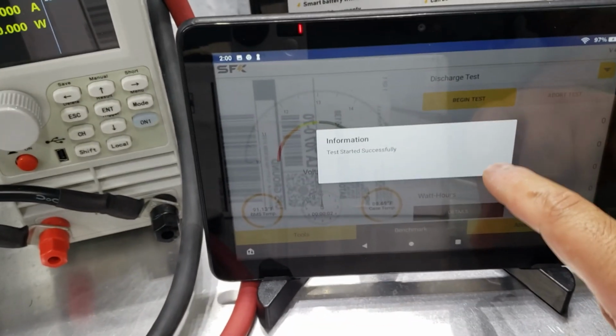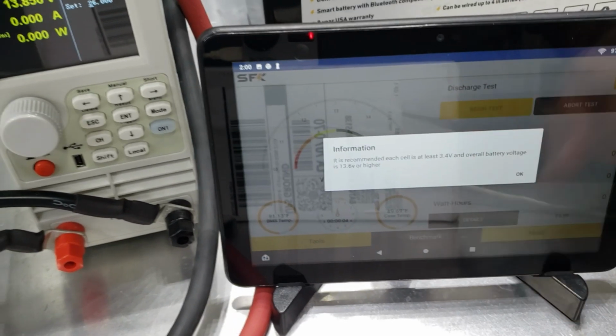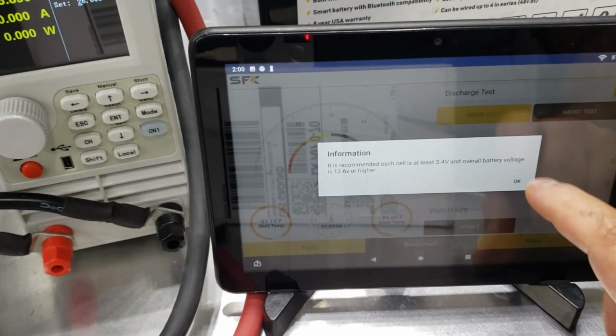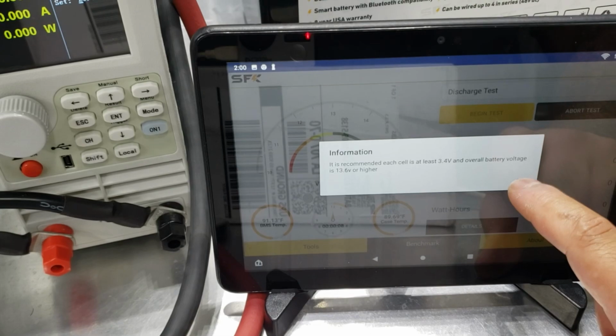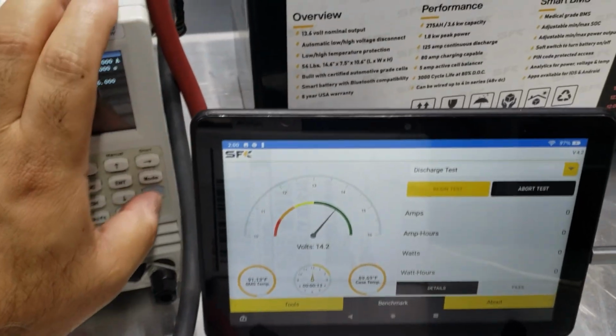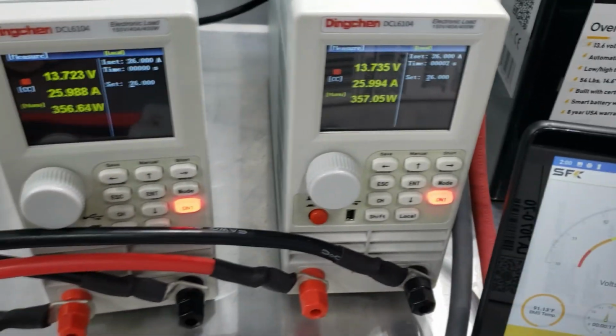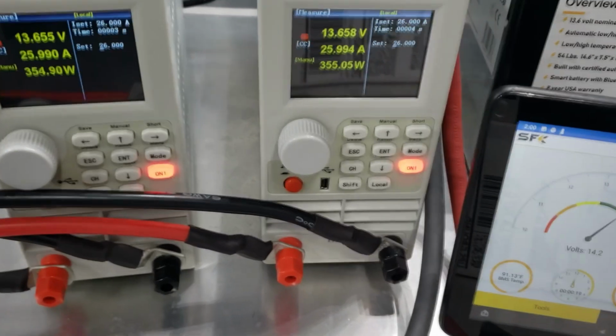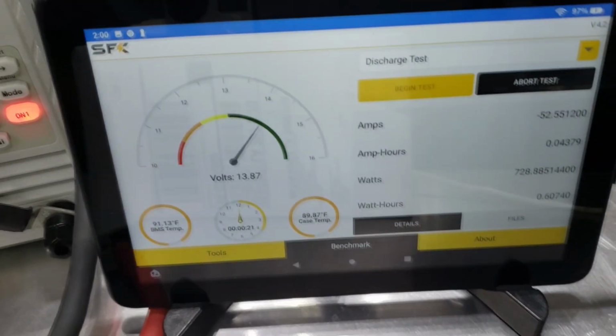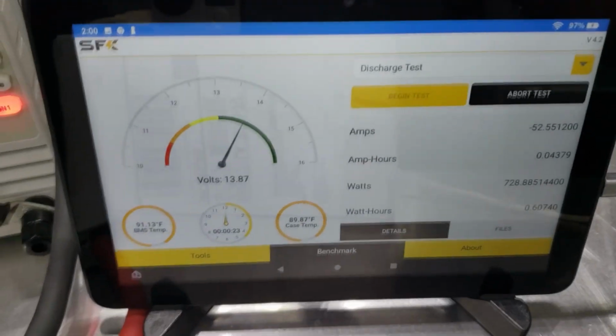It's going to say test started successfully, and then it makes sure each cell is 3.4 or higher, or 13.6 total. We'll hit OK. Now the system is waiting for you to apply the load, so we hit on for the first one and on for the second one. Now we have two loads applying.